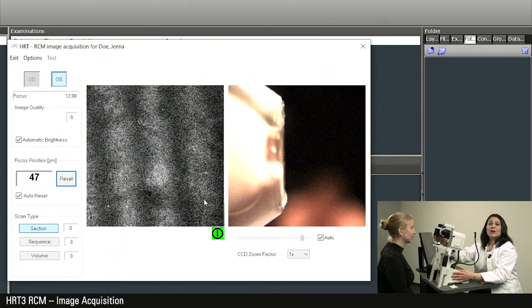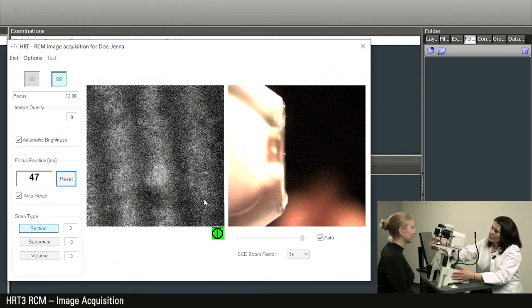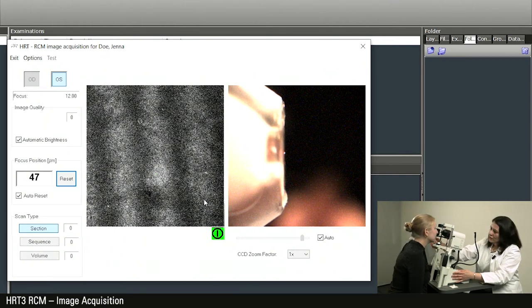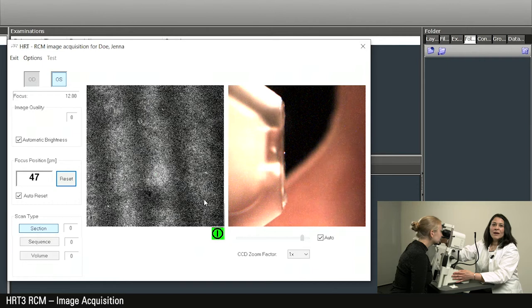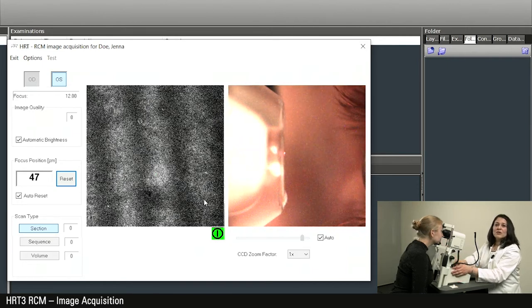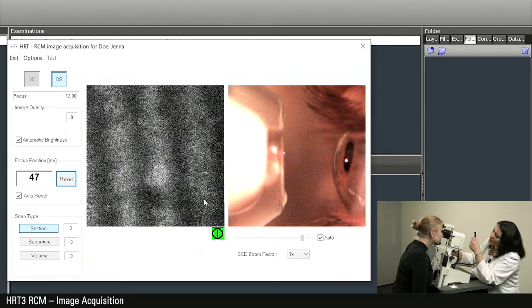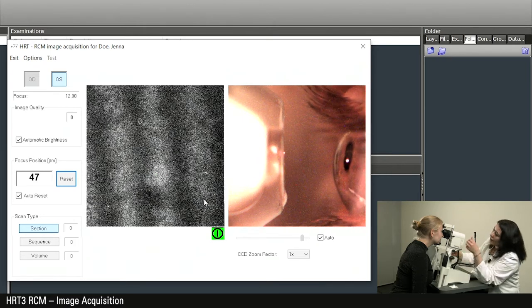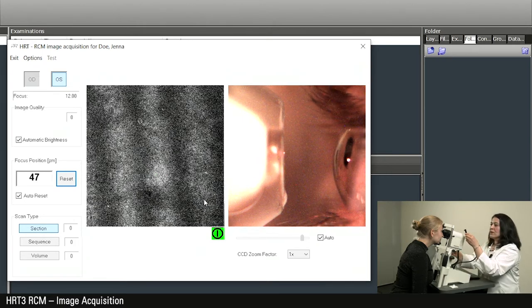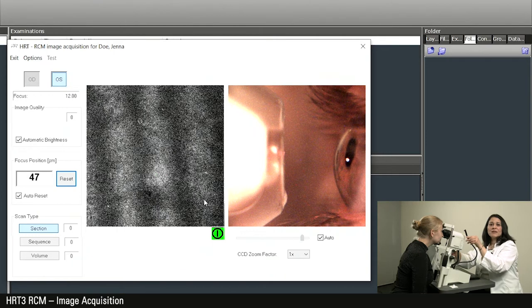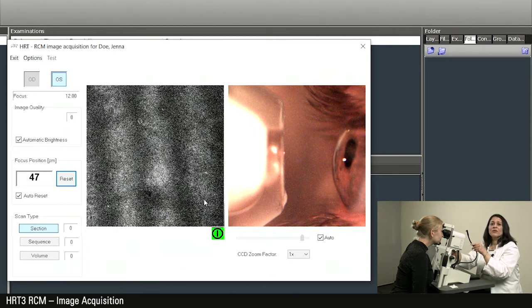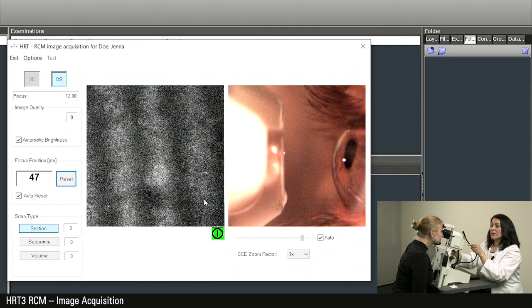Now that we have adjusted the CCD camera, the patient can put the chin on the chin rest and we will move the scanning laser camera towards the patient until the cornea is five to ten millimeters away from the tomo cap. To assist the patient, you can place a fixation light so that it is in the optical axis of the patient and ask the patient to fixate it during the examination.